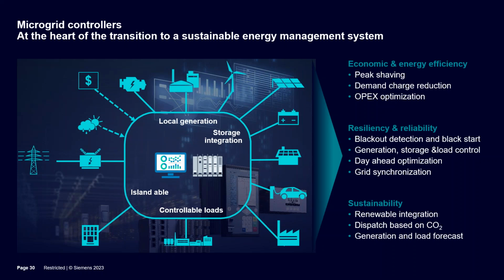So that happens automatically, and in most cases, folks on that campus or in those buildings don't even see a blip in their service. It's a very seamless transition. The microgrid controller operates the local assets, the local generation, to serve the load, and when it senses the grid is back, it resynchronizes with the grid. It goes through a set of rules to shut down local generation, and then we go back to parallel operation.